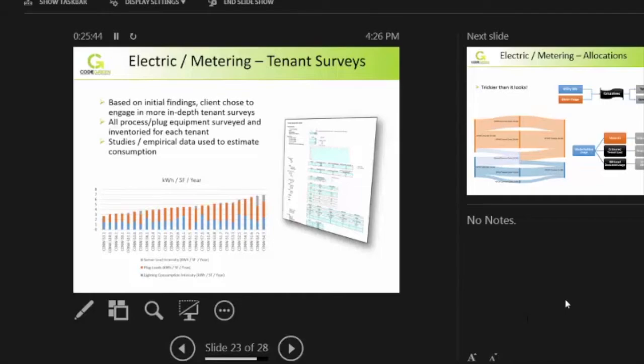If you think a meter is metering a certain space and you know everything within that space, is there a way to estimate whether you're in the right ballpark of usage? This is a process we developed: we inventory all the equipment at the building—printers, computers, plug loads, lights, everything you'd typically find in a tenant space. From that, you extrapolate: if it's a well-run space, how much energy will it use? If it's a poorly run space, how much will it use? And from that, you try to determine how accurate the existing meters are.